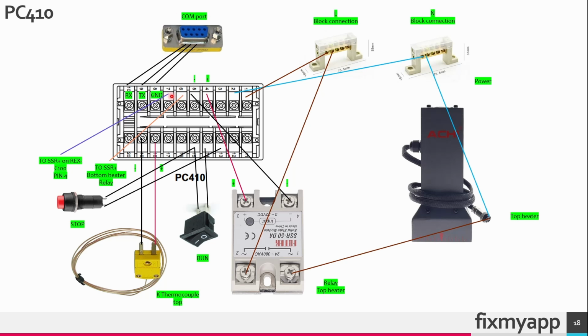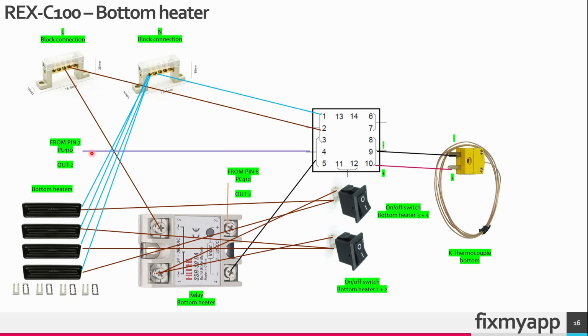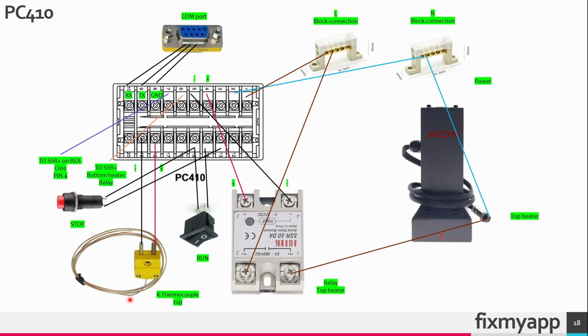Terminal 8, 9 and 10 are used for the serial communication. Terminal 6 and 7 is the output 2. So terminal 6 will go to the solid state relay for the bottom heater plus connection. Terminal 7 will go to the bottom heater temperature controller on terminal 4. Terminal 7 from the PC410 will be connected to terminal 4. And the terminal number 7 that comes from the PC410 will be connected to this positive side of the solid state relay.